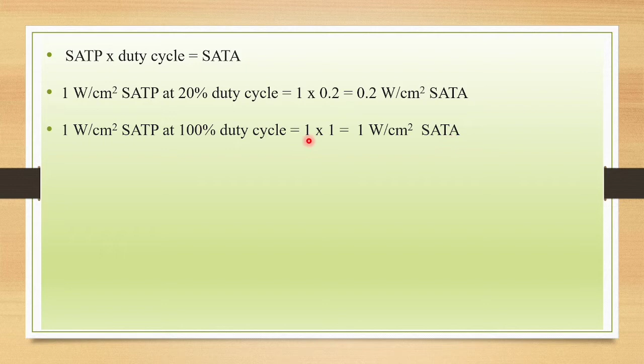And this is the pulsed ultrasound, and this is the continuous ultrasound. In continuous ultrasound, spatial average temporal peak intensity and spatial average temporal average intensity will be the same. For example, the spatial average temporal peak intensity is 1 watt per centimeter square, and in continuous mode we have 100% duty cycle. So 1 into 1, the spatial average temporal peak intensity and spatial average temporal average intensity will be the same, that is 1 watt per centimeter square each.